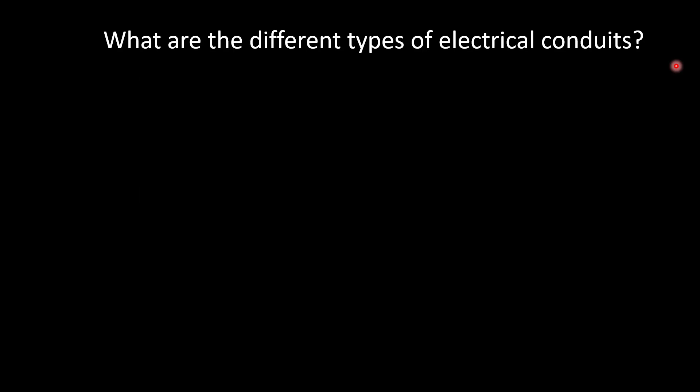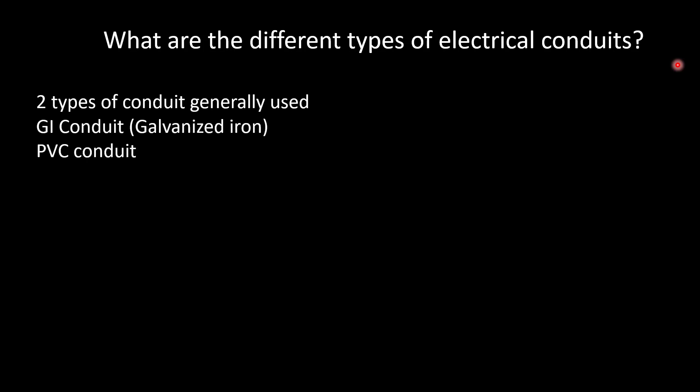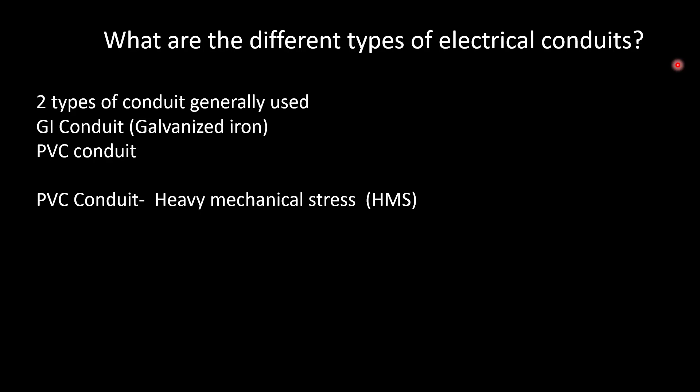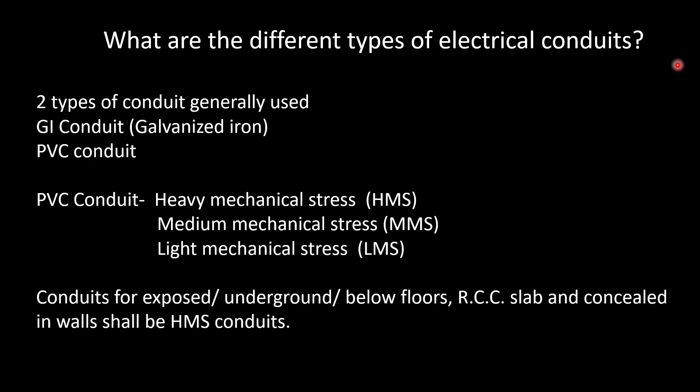What are the different types of electrical conduits normally used? We use two types: GI (Galvanized Iron) conduit and PVC conduit (a plastic conduit). PVC conduit can be classified into three types: Heavy Mechanical Stress (HMS) conduit — thicker and can sustain more mechanical stress; Medium Mechanical Stress (MMS) conduit; and Light Mechanical Stress (LMS) conduit. Conduits for exposed, underground, below floor, RCC slab, and concealed-in-wall installations shall be HMS conduits — also commonly called heavy duty conduit. GI conduits are normally used in exposed installations such as parkings and inside shafts.